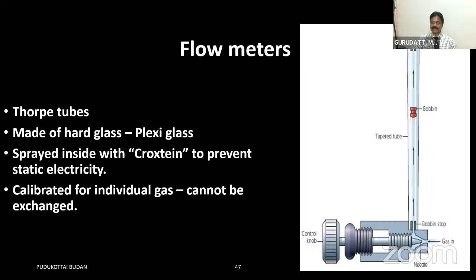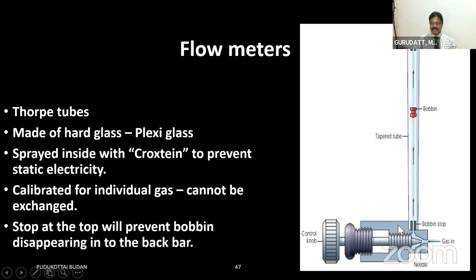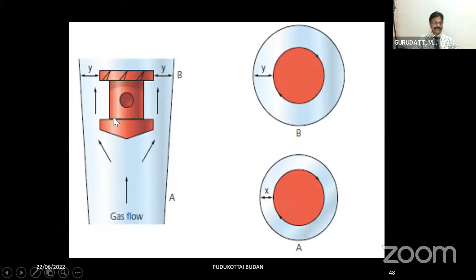And another thing you should always remember, the calibration of this flow meter is done at sea level, that is 760 millimeters environmental pressure, and at 20 degrees, that is the room temperature. The other thing about these flow meters is that they have stops at the bottom and at the top. This is mainly to ensure that the bobbin or the float does not escape into the back bar. So, again as a safety feature, we have the bobbin stops at the top and at the bottom. Now you can see this is the float and the bobbin.